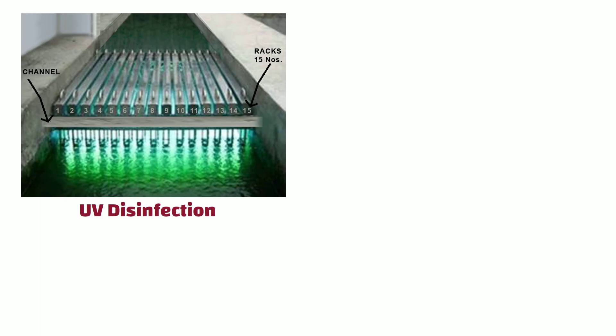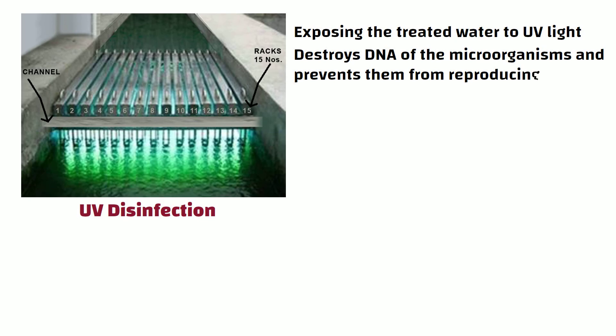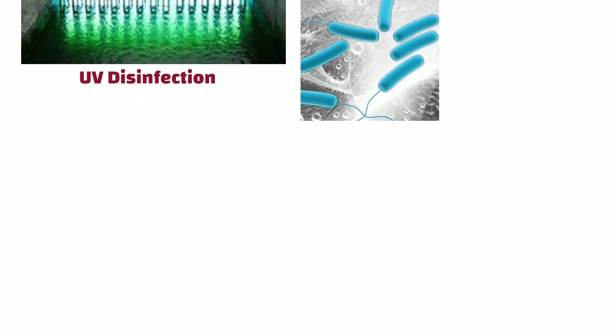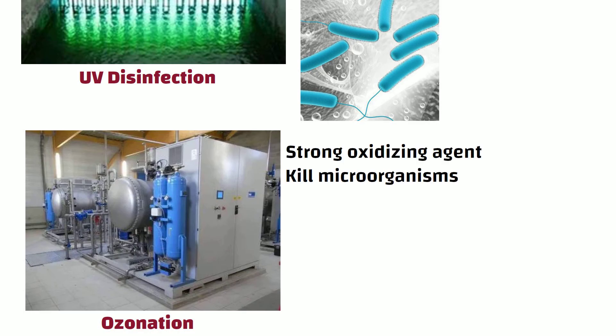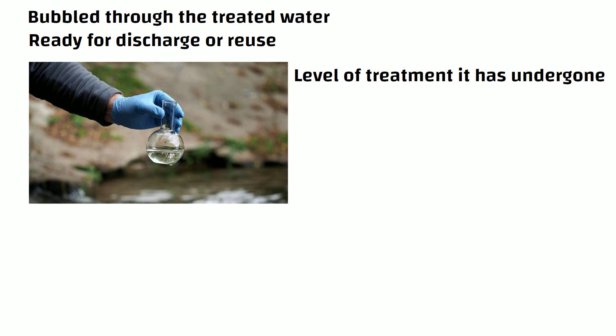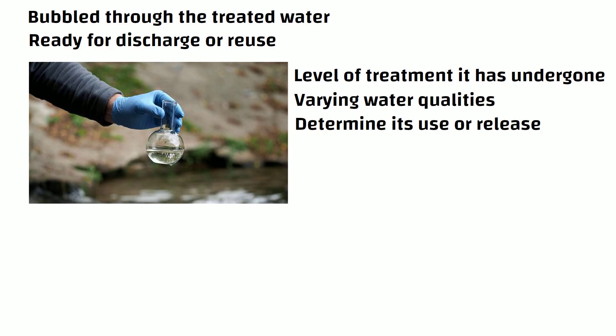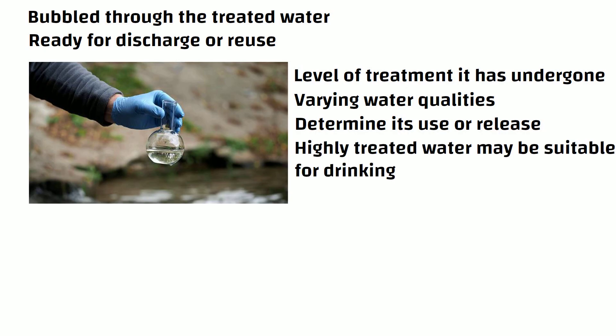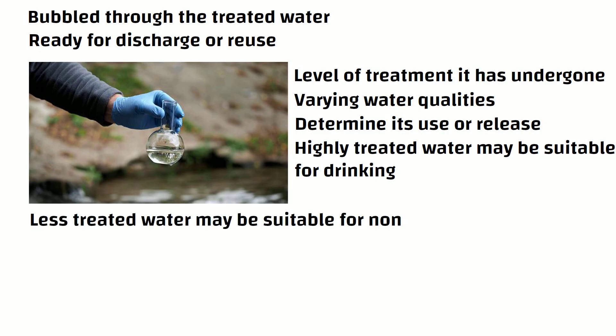UV disinfection involves exposing treated water to UV light, which destroys the DNA of microorganisms and prevents them from reproducing; exposure time is carefully controlled. In ozonation, ozone — a strong oxidizing agent — is generated on site and bubbled through the treated water to kill microorganisms by destroying their cell walls. After disinfection, the treated wastewater is ready for discharge or reuse. The quality of treated water depends on the level of treatment it has undergone — highly treated water may be suitable for drinking, while less treated water may be suitable for non-potable uses such as irrigation.